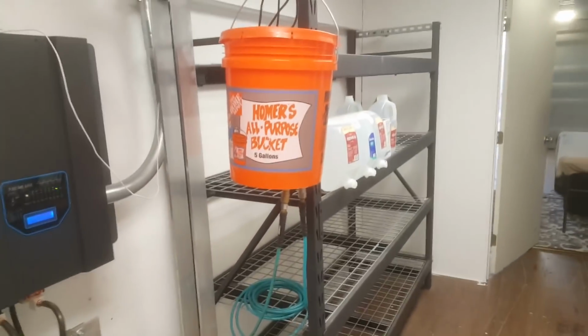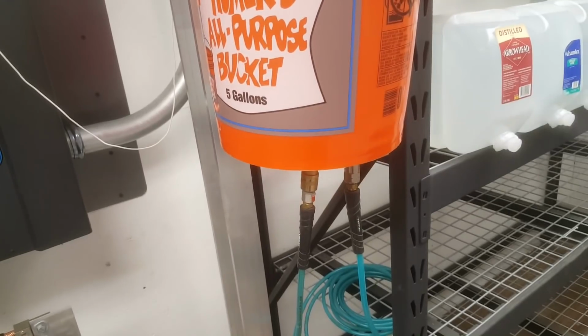This is my battery filler. I use this because you need to check the electrolyte levels in these batteries. All I did was I took a 5-gallon Home Depot bucket and epoxied in 2 quick disconnect air fittings. And originally I had this set up so I can put about 10 psi of air into the unit. That way it could push the water to these top batteries, but it actually takes a significant amount of air pressure in order to push water through the hose. And what would often happen is the lid would come off. So it was a great idea, but in practice it didn't work.